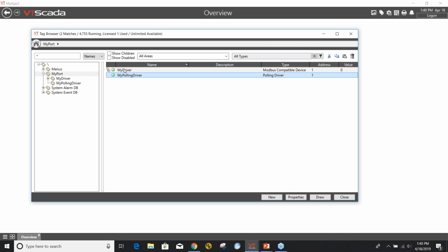Similarly, if you're doing something on TCP, then you can use a VPN IPsec tunnel, which is very common. That allows you to do point-to-point encryption for these links, and we see that quite commonly used. But serial is still kind of an unknown, a bit of a Wild West world, so serial over radio. There are other protocols that utilize security, and Modbus is just not one of them.